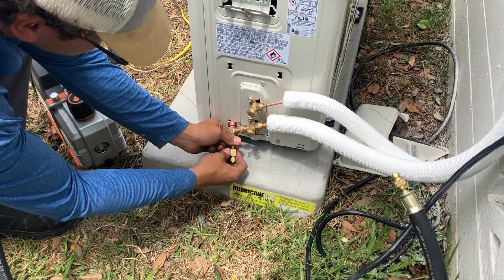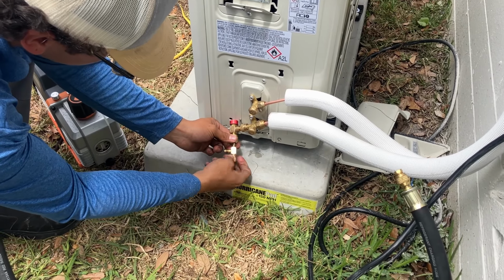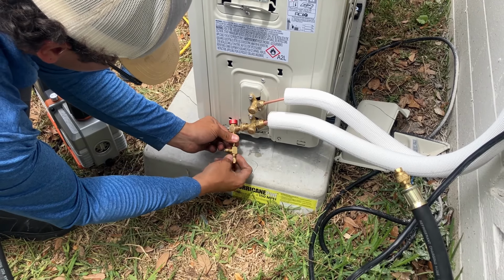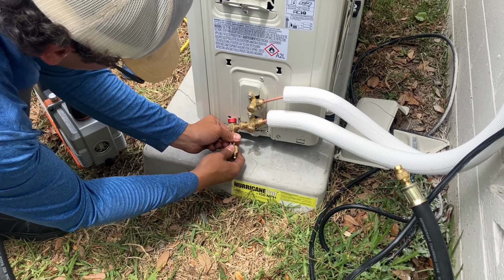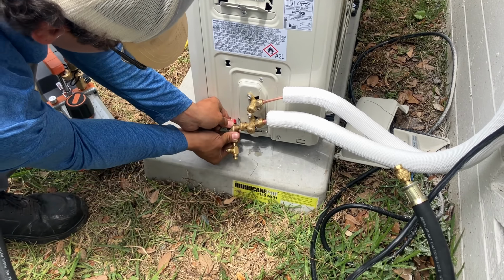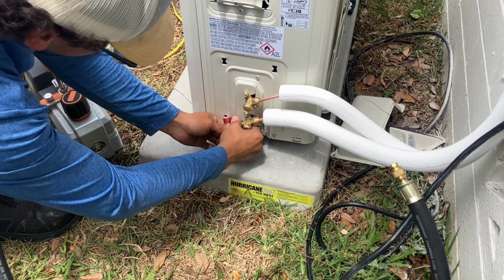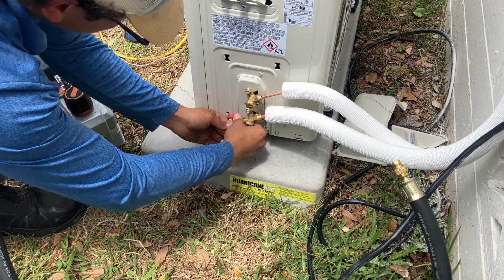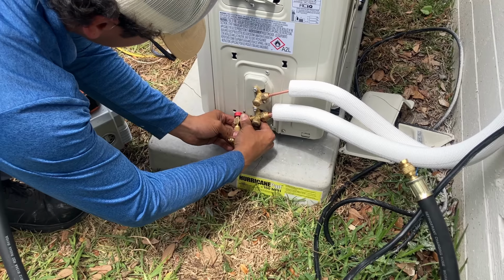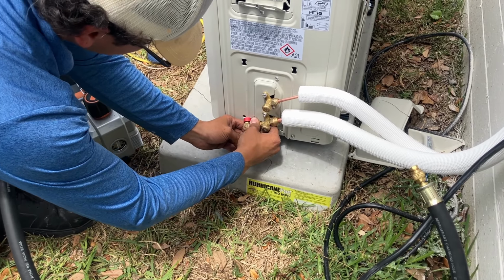It's not really a long line, maybe 12 feet, 10 feet if that. So this will pump down quickly, even with that Schrader core in place. Setting a little valve there with a T to add your micron gauge.